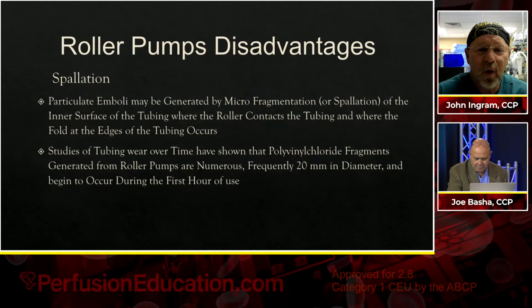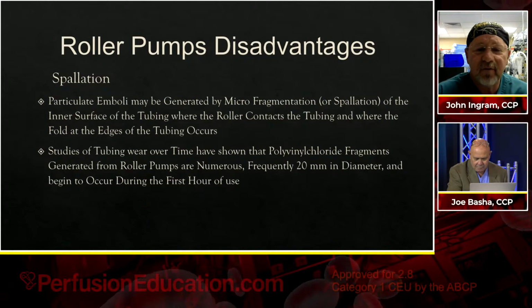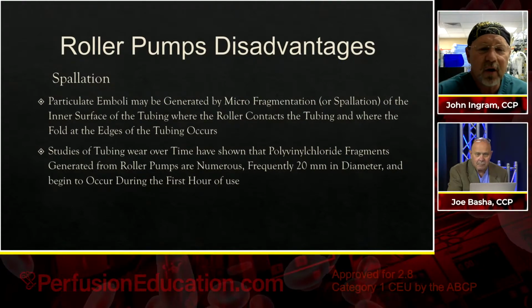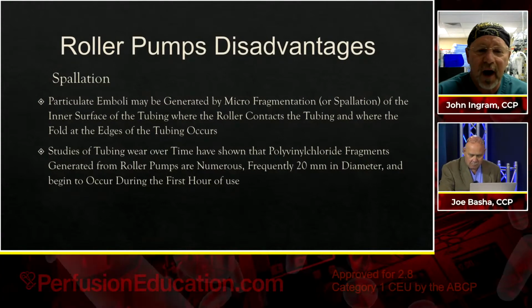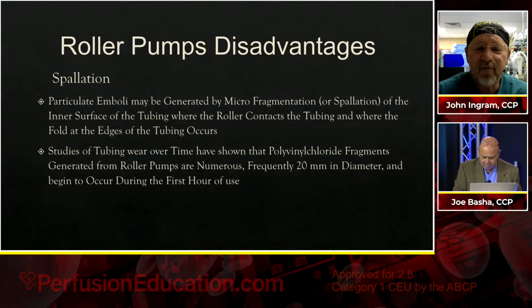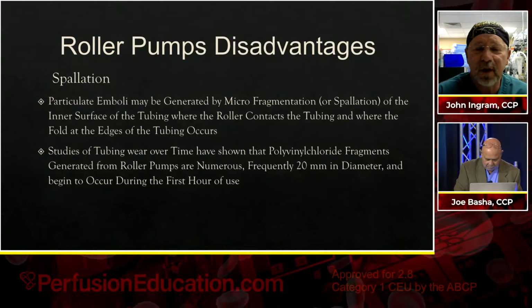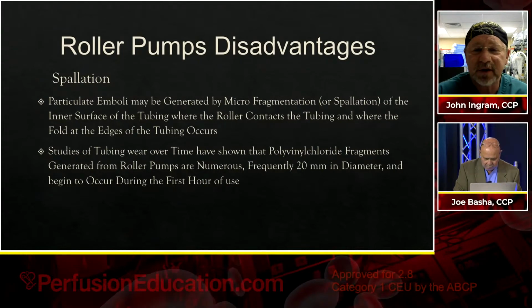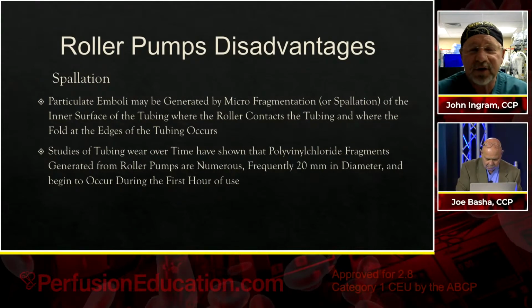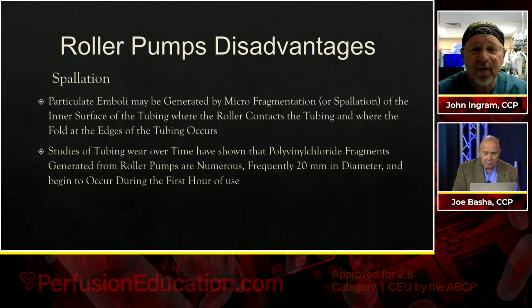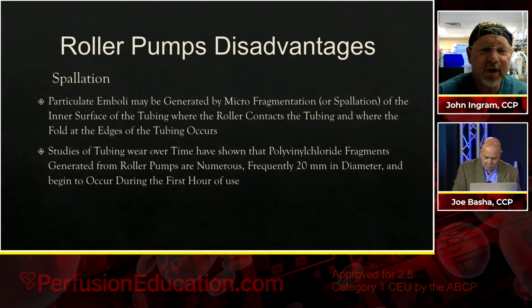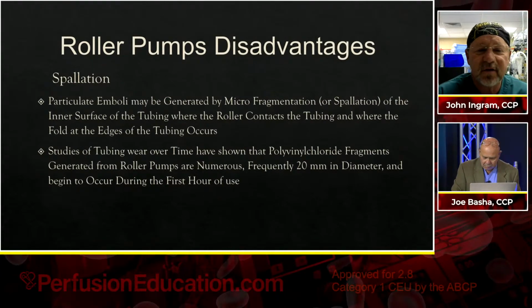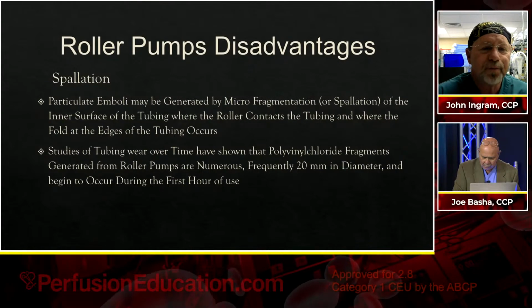Studies of tubing wear over time have shown that polyvinylchloride fragments generated from roller pumps are actually quite numerous and frequently as large as 20 millimeters in diameter, which sounds pretty scary. That would never make it past your arterial line filter, thankfully. But they actually begin to occur as early as in the first hour of use.